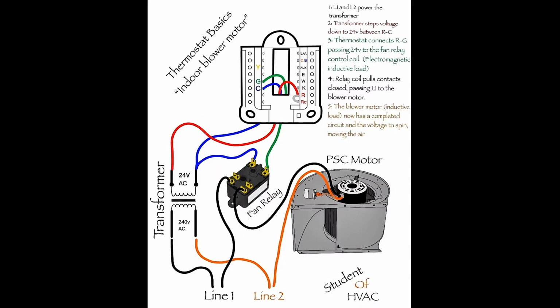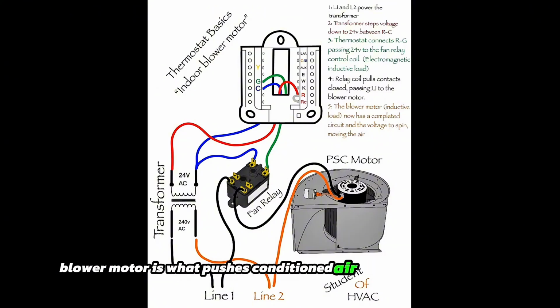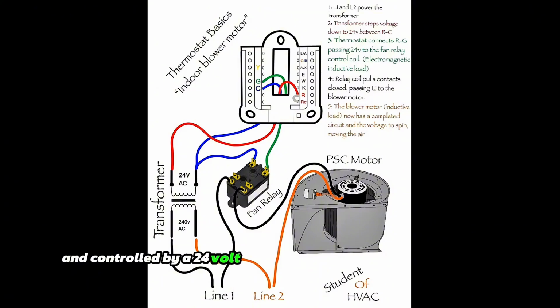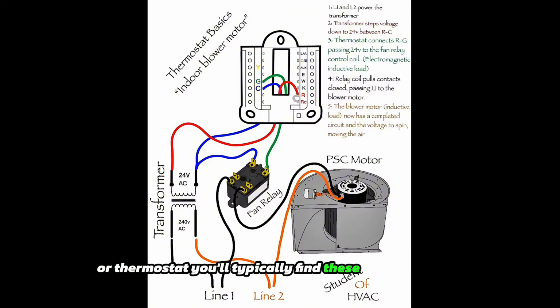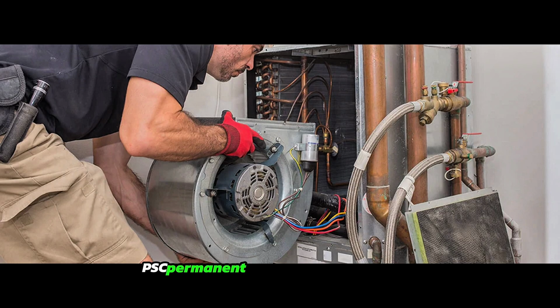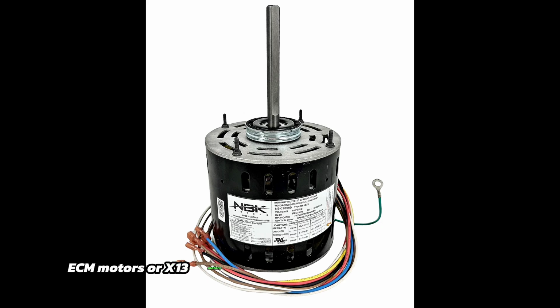Let's begin. Blower motors inside the air handler. Your indoor blower motor is what pushes conditioned air through the ducts. It's powered by high voltage, usually 240 volts, and controlled by a 24-volt signal that comes from the control board or thermostat. You'll typically find these three types: PSC, permanent split capacitor motors, ECM motors, or X13 motors.